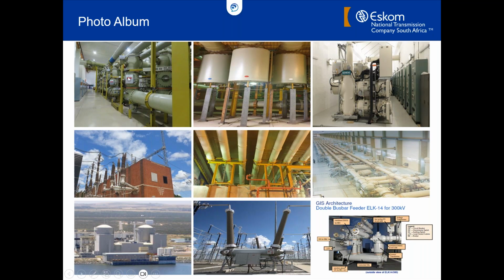For instance, here at the top, that is on the 400 kV network, Koeberg substation. This is Drakensberg, shown in the middle top and center pictures. Although Drakensberg substation has only got 6 bays, it's got quite a high number of SF6. One reason is that we transport the electricity by means of a bus duct from the bottom, where it's generated, up to the surface level onto the feeders. Those bus ducts, there are 6 of them, running up a length of 120 meters, and that also contributes to a high amount of gas being used.